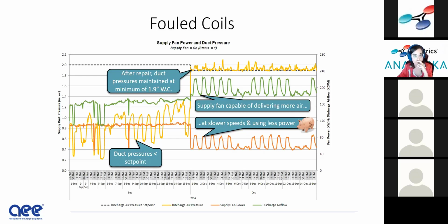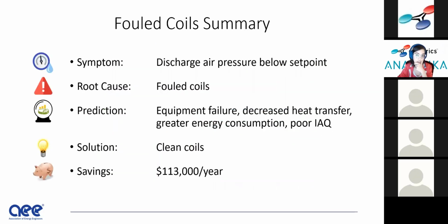The problem here when you have fouled coils, besides energy waste, is it's really not good for equipment. It'll degrade the equipment, right? You're going to be running your fans at higher speeds. I'll go to the next slide. You can blow your fan motor. You have decreased heat transfer, all that stuff. You're trying to work harder to push air through the piece of equipment. Indoor air quality is a problem.